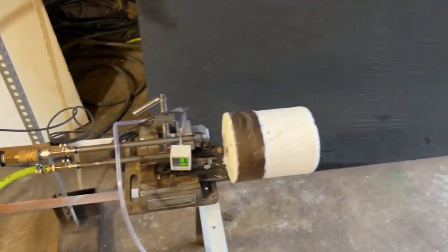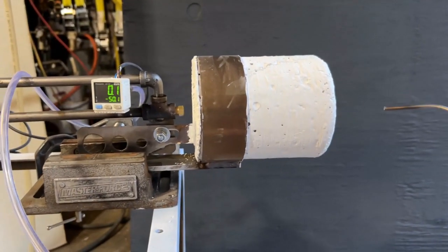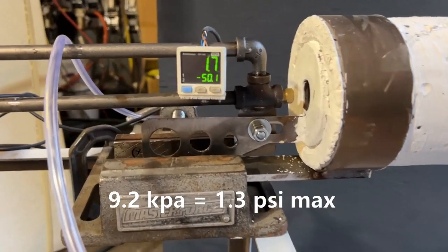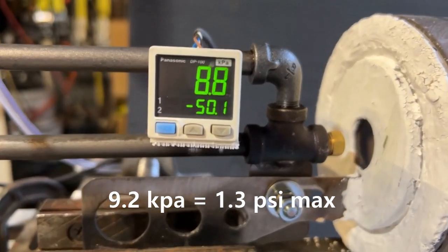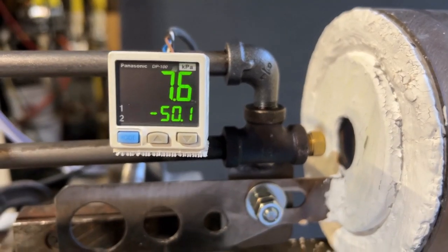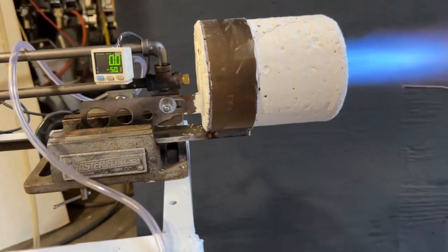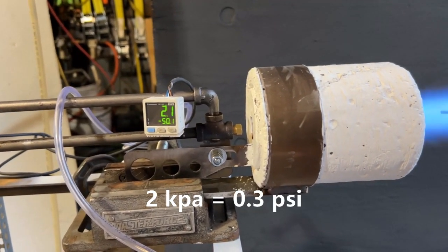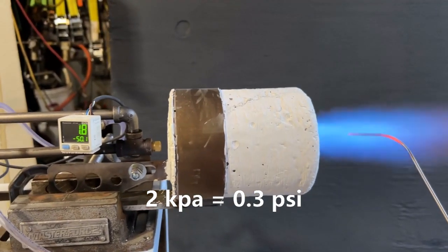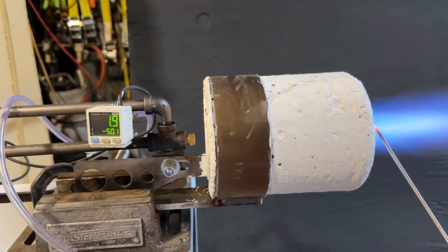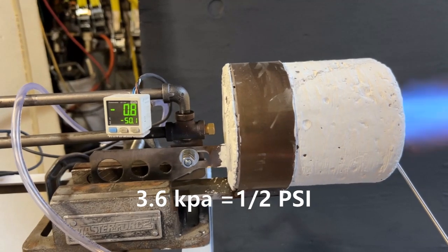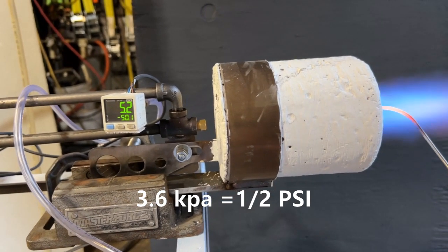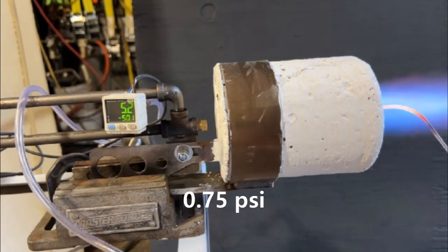Now we're going to do some pressure transducer testing here. I've got some theories on why these burners are so loud and I've always wondered what is the internal pressure inside of one of these things when it's running - is there vacuum voids, things like that. Today we're going to find out and it's pretty interesting. Matter of fact there's both pressure and vacuum inside this combustion chamber simultaneously, which is why it sustains combustion. You have regions of low pressure that is causing a flow of high pressure going to it. And right there we hit 0.75 PSI inside of that combustion chamber.